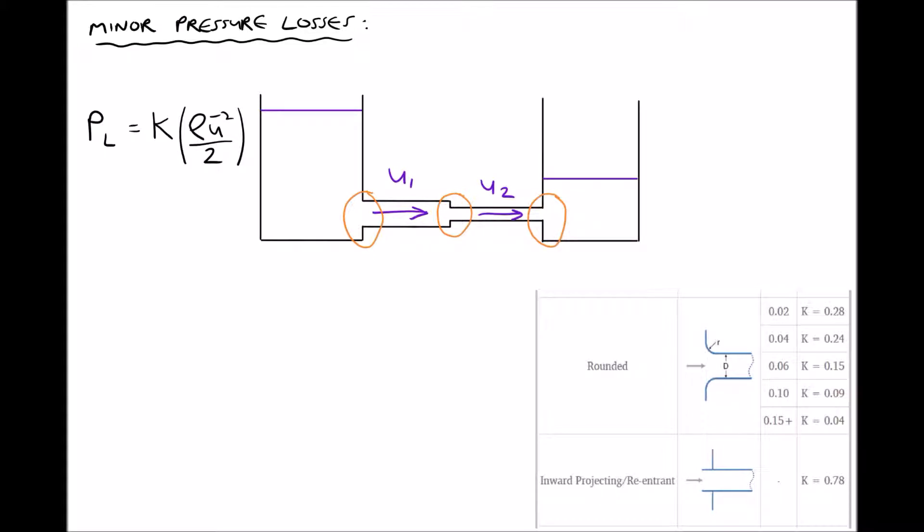There's only really one formula that we need for calculating minor pressure losses. We see on the left hand side where the pressure loss equals K times ρ times ū squared over 2. So PL represents the pressure loss, K is something called the resistance coefficient, ρ is the density of the fluid, and ū bar is the mean velocity squared.